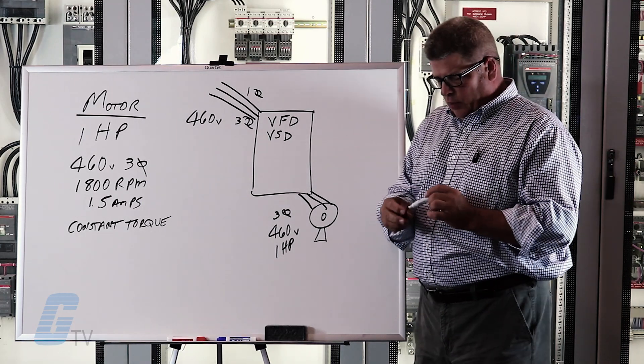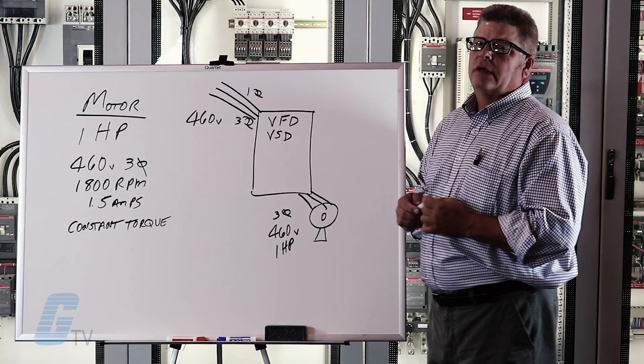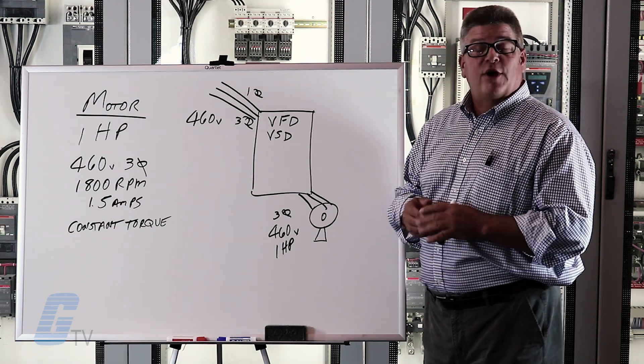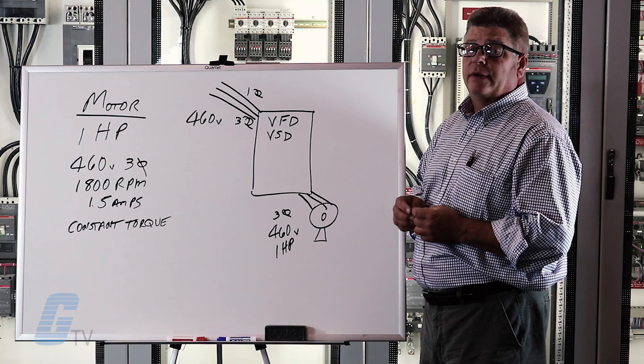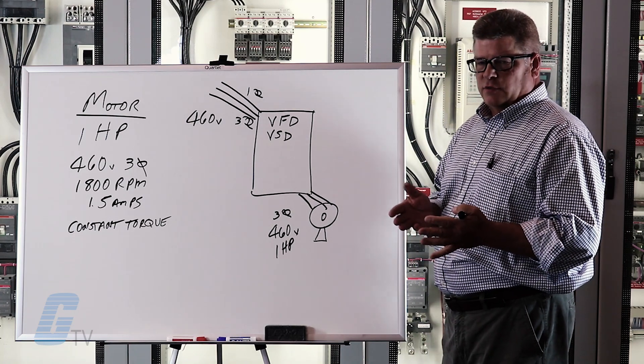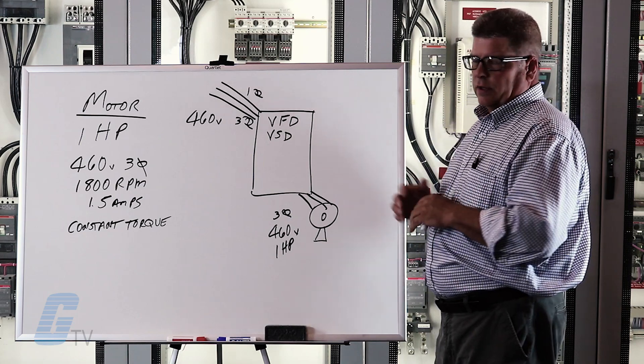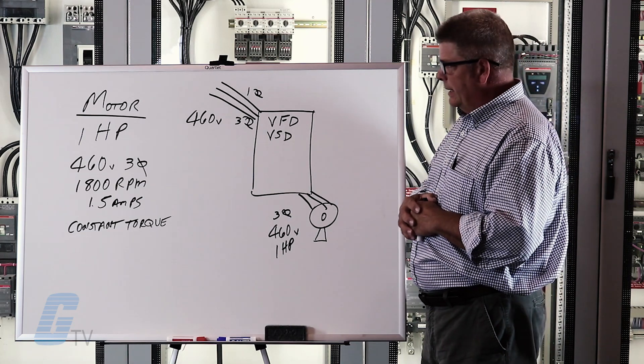Constant torque means that the motor needs to provide its full torque right from zero speed up to its full speed rating. The other option would be a variable torque load like a fan or a pump where you need minimal torque at zero speed and maximum torque at high speed. In our case today it's a constant torque conveyor that we are working on.